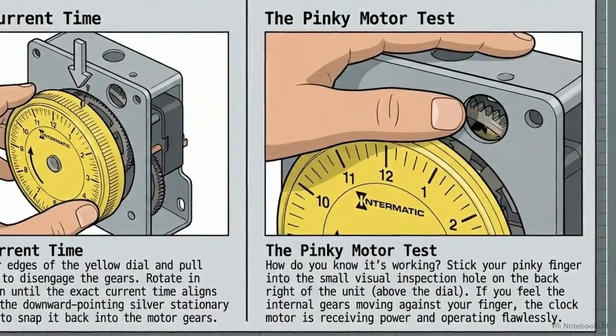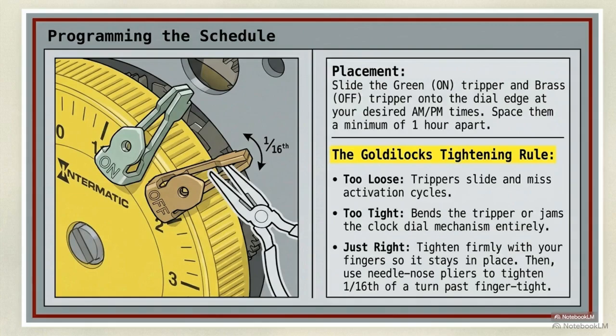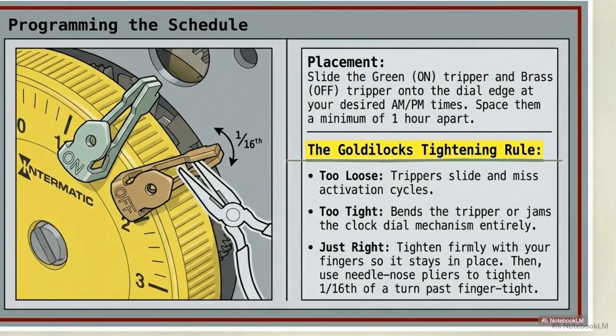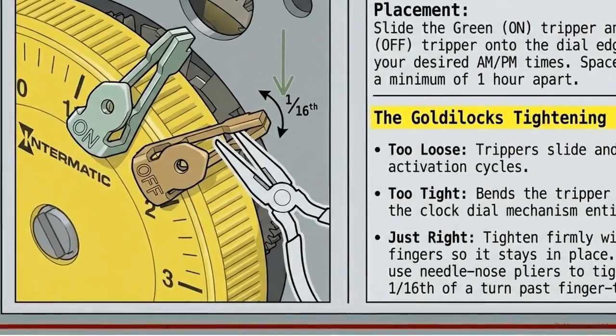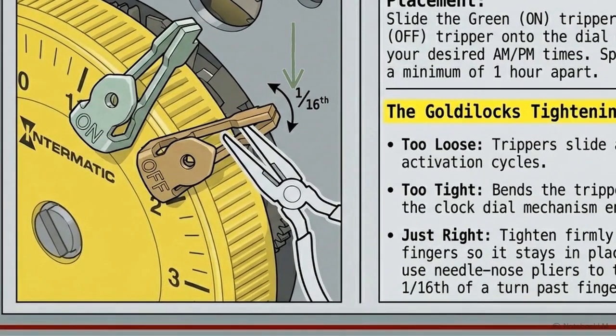This diagram shows how to set your daily schedule. Slide the green on tripper onto the edge of the dial at the time you want the power to start, and place the brass off tripper at the time you want it to stop. Secure them using the Goldilocks Tightening Rule. Tighten them firmly with your fingers, then use needle nose pliers to turn the screw exactly 1/16 of a rotation more. Too loose, and the trippers slide right past the activation switch.